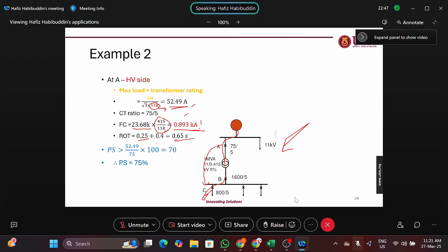Find the plug setting, use this equation, 75% of that. 75, it is going to be 56.25. Again, we are having the issue of allowing for some overload. That is your judgment. Okay, so the only difference here is this.